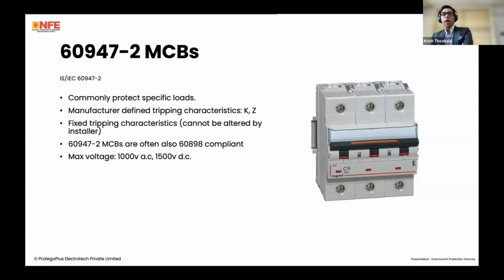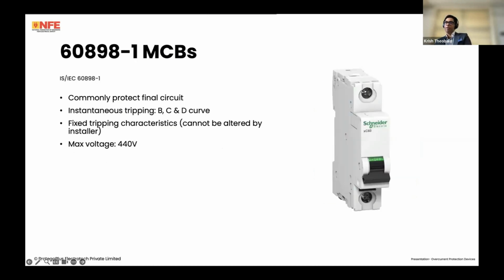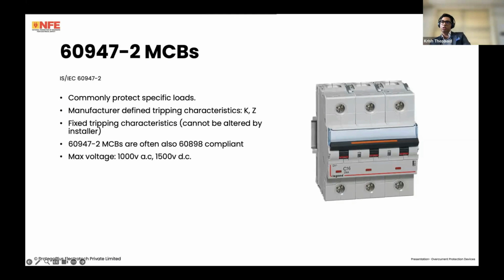We'll have a look at this. Also, it's very common to have 60947 Part 2 MCBs that are also 60898 compliant. So, for instance, if you've got a single MCB, you'll have two certifications. That will be mentioned: two product standards, 60898 Part 1 and 60947 Part 2. This could possibly be because it's a load with a regular characteristic, but the fault currents are higher than what the 60898 is certified for. So then it would be dual certification.